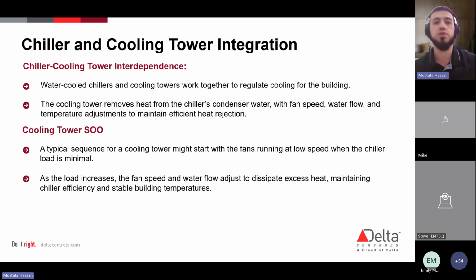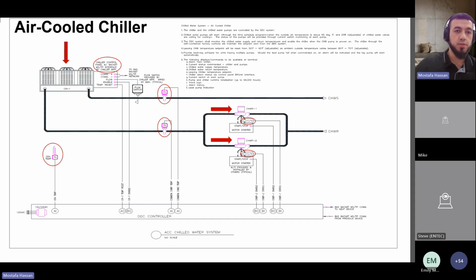Chillers and cooling towers are two systems that work together to expel heat from your water system to allow chilled water to reach the building. Your cooling tower expels the heat from the chiller supply. Emily referenced these two systems, and in a second we're going to go through an air-cooled chiller example. This is how the building uses water to regulate cooling. Your cooling tower takes the heat out, and then your chiller supplies use pumps to supply chilled water to the building. The difference between this air-cooled chiller and the last example is that in the last example the chiller needed the cooling tower to expel the heat through the water. In this case, it's an air-cooled chiller.